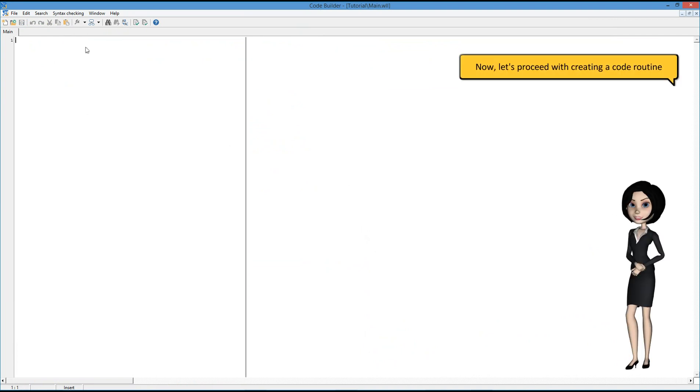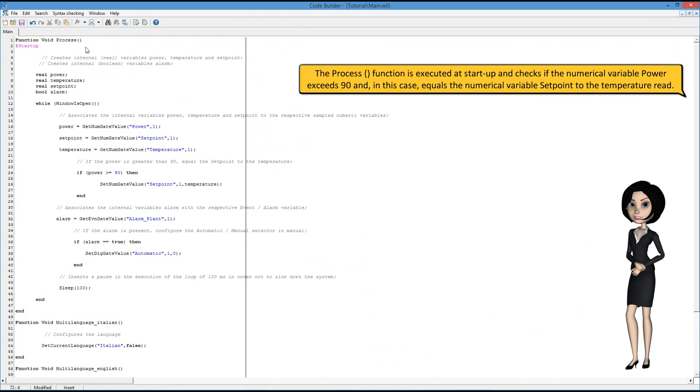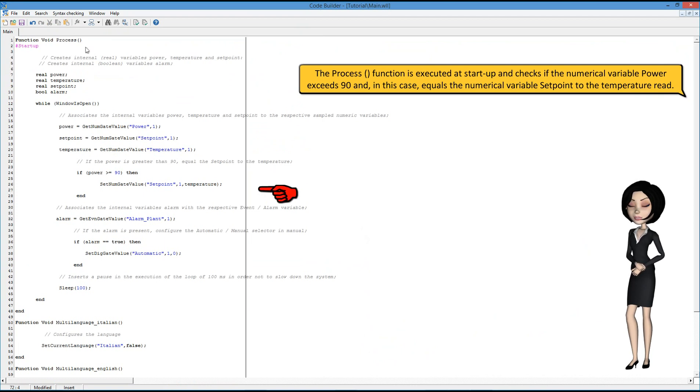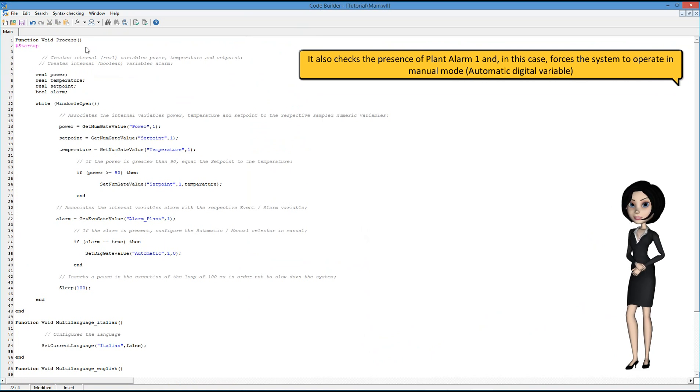Now, let's proceed with creating a code routine. The process function is executed at startup and checks if the numerical variable power exceeds 90 and, in this case, equals the numerical variable setpoint to the temperature read. It also checks the presence of plant alarm and, in this case, forces the system to operate in manual mode, automatic digital variable.